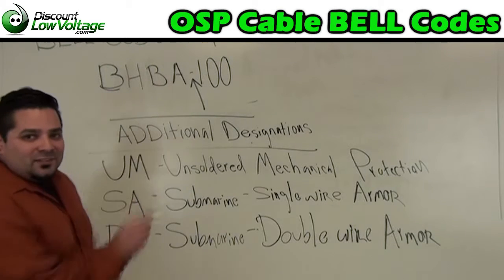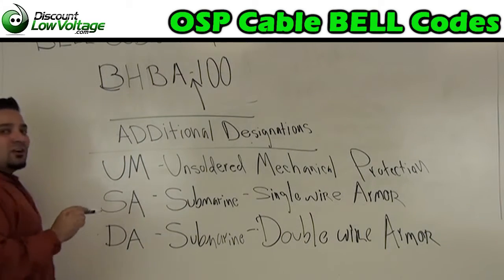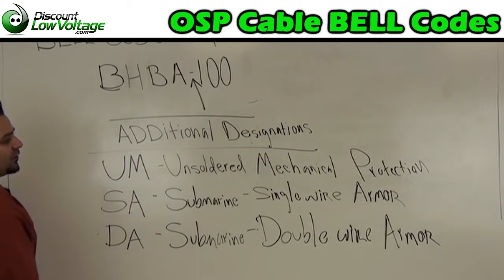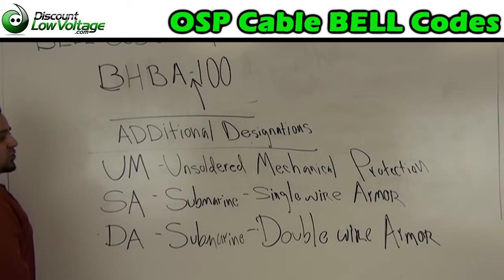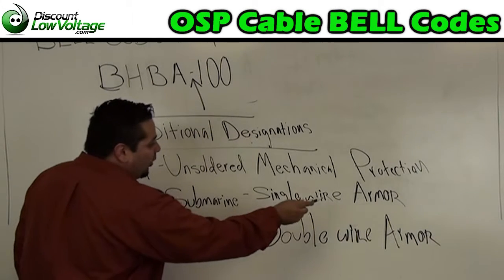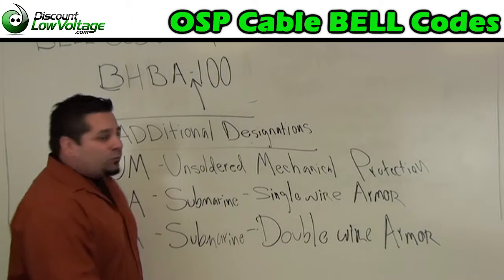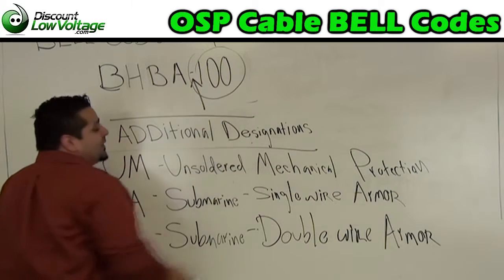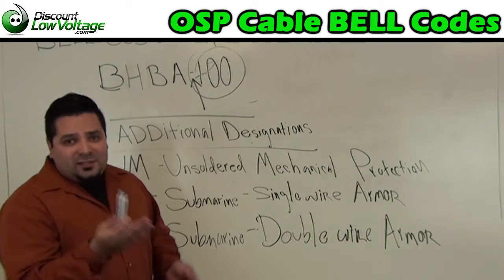You're going to have four designations, but you may have additional designations. That type of cable is not too common. But you're either going to have a UM, which is an unsoldered mechanical protection code, or an SA designation after your fourth letter, which is a submarine single wire armored, or a DA, which is a submarine double wire armored. And don't forget, after your code you have your 100, which designates how many pairs of cable — 25 pair would be 25, 12 would be 12, and so on.